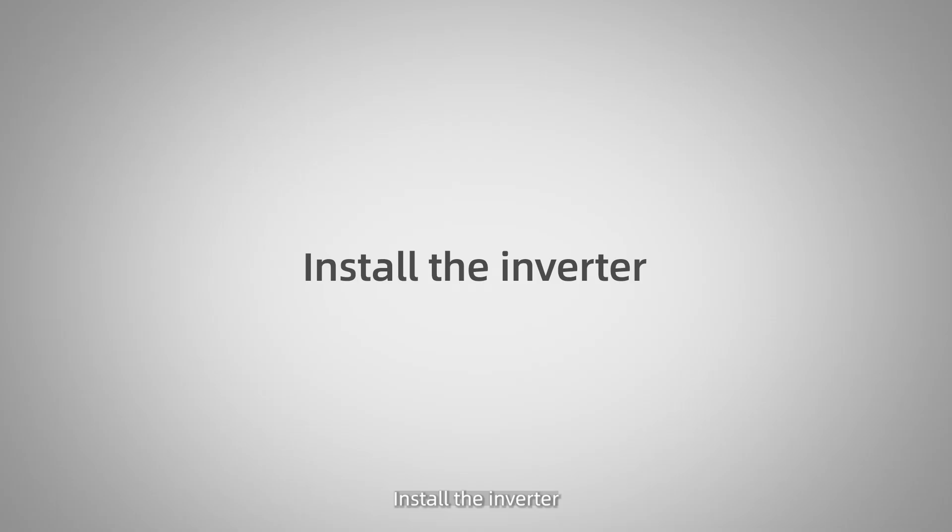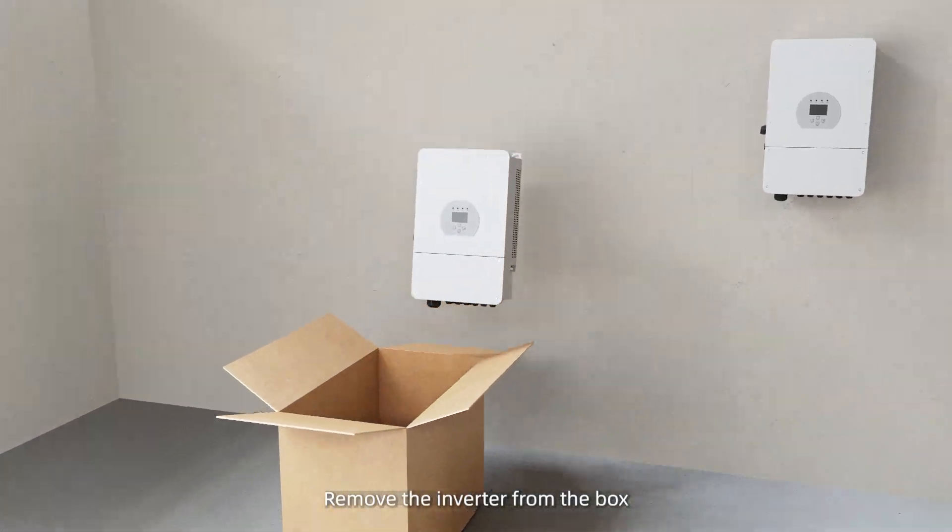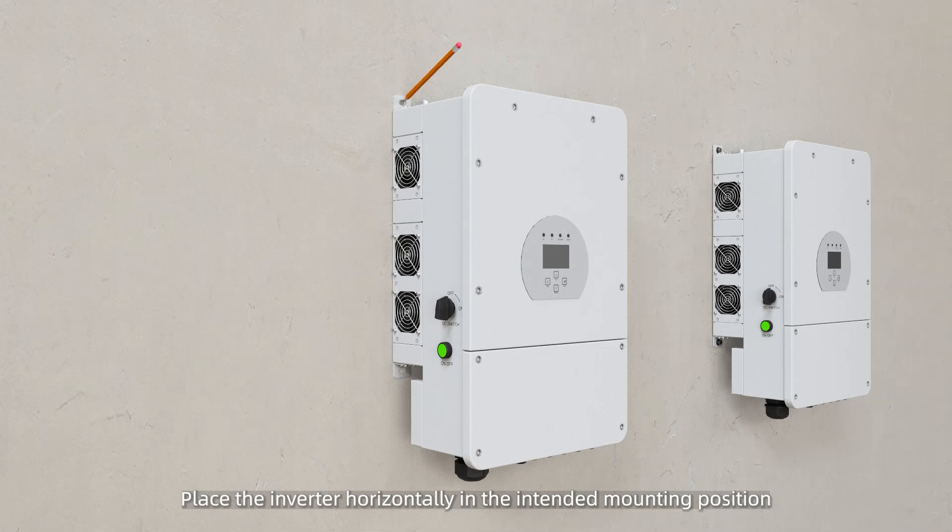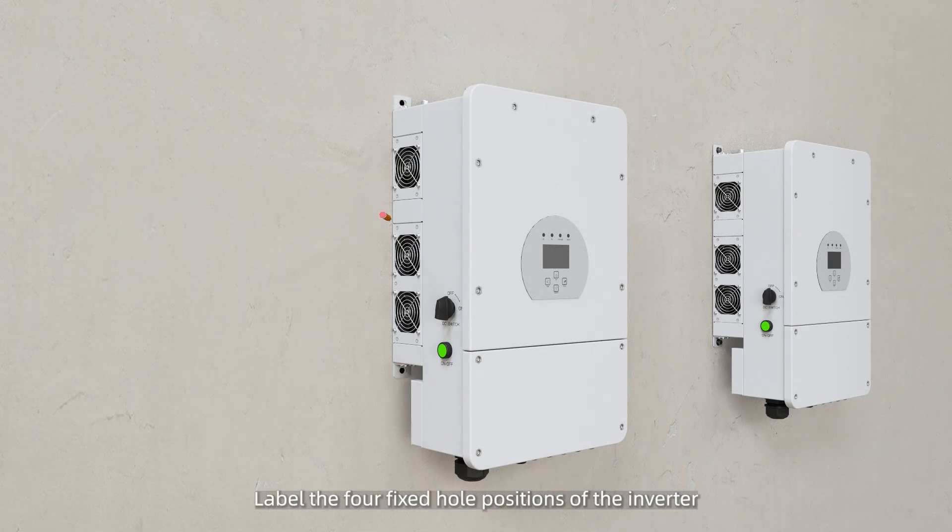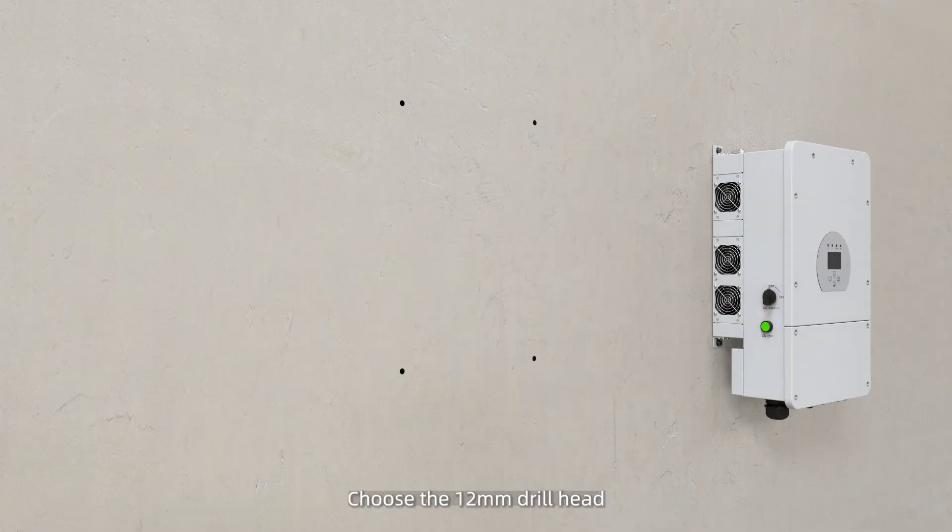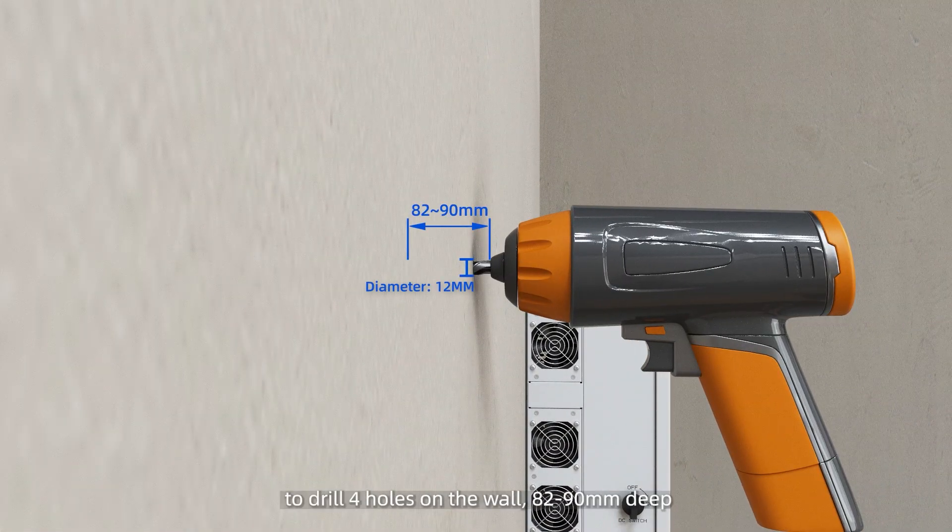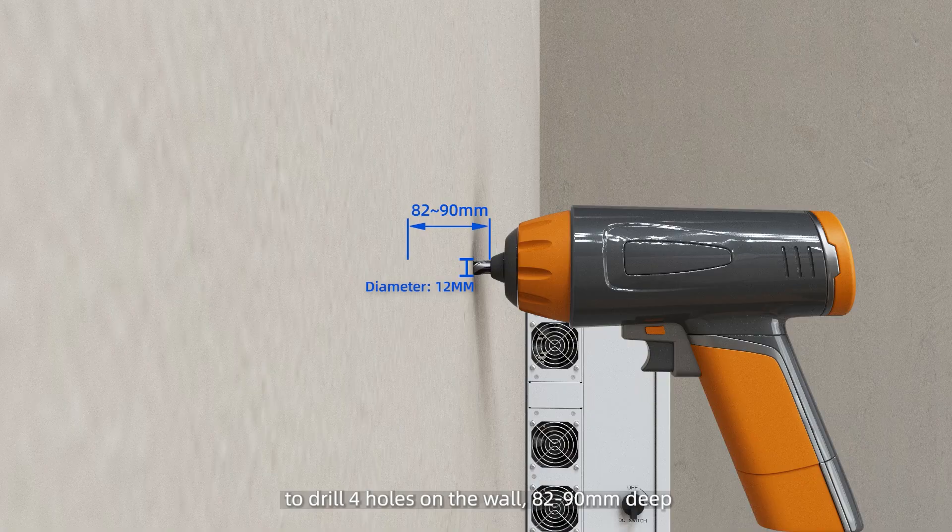Install the inverter. Remove the inverter from the box. Place the inverter horizontally in the intended mounting position. Label the four fixed hole positions of the inverter. Choose the 12mm drill head to drill four holes on the wall, 82 to 90mm deep.